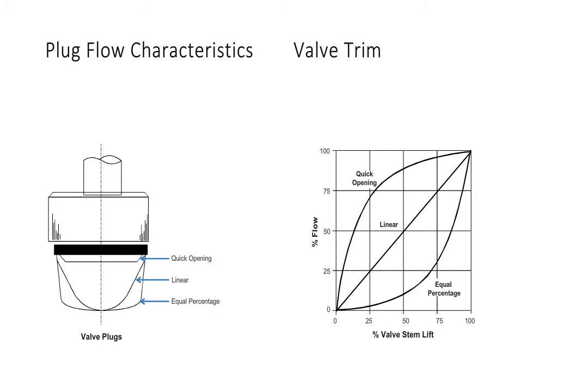Pause for a moment and ask yourself, which plug would you want in a valve to control water flow? Many people choose the linear shaped plug as the logical choice. Linear is the incorrect choice. As we shall discover, the equal percentage plug is most often the best choice for good flow control.